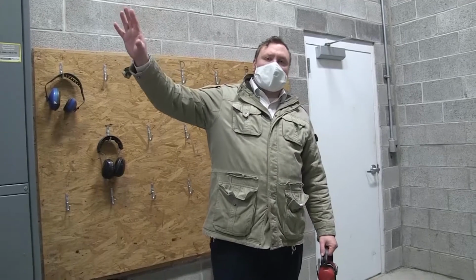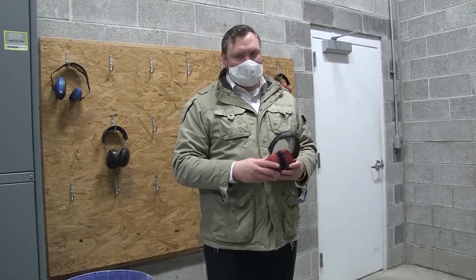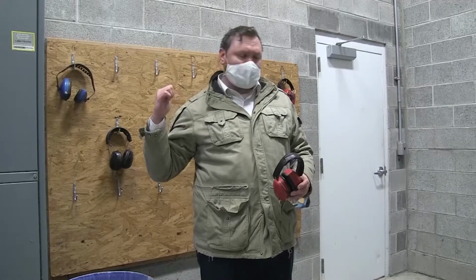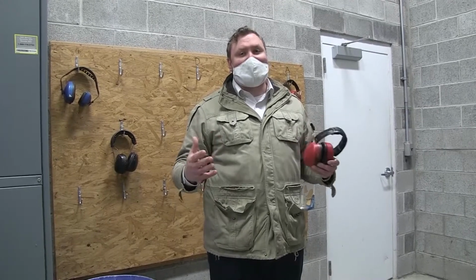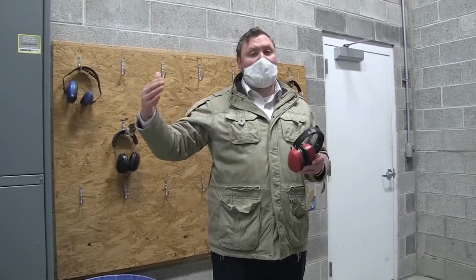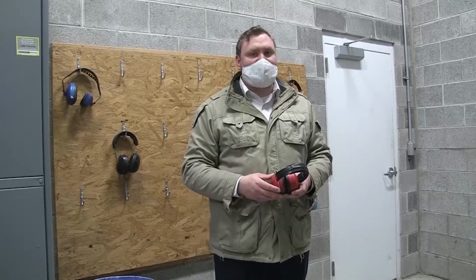So we just left the activated sludge basins. I had mentioned the air that was required for those bugs, for that microbiology to do what they need to do. We're just going to take a quick jog into our blower room. I'll show you the blower that actually does that work. It's a 700 horsepower motor, so it's a lot of electricity. Each one of these blowers can move upwards of about 13,000 cubic feet per minute, again against that pressure I had mentioned of about 7.5 psi.